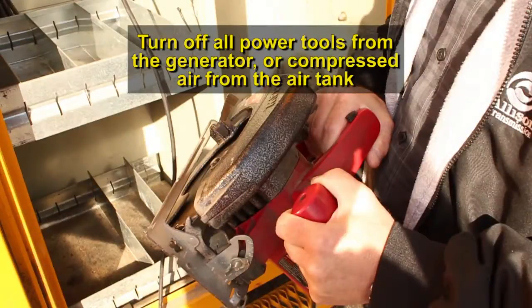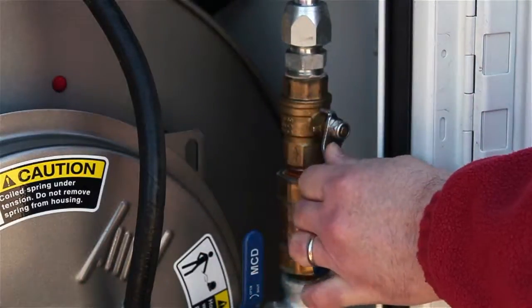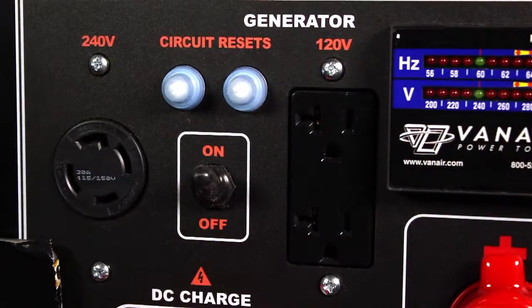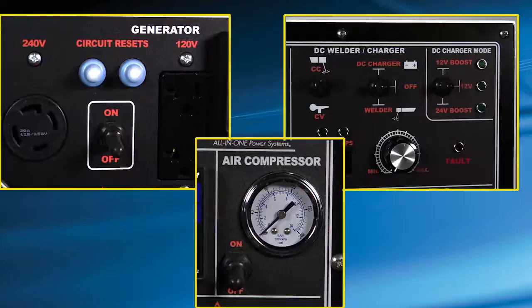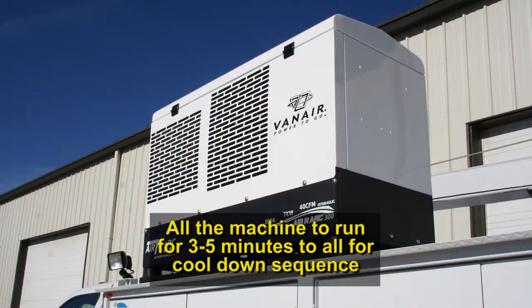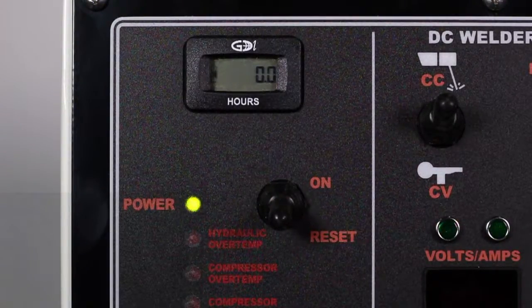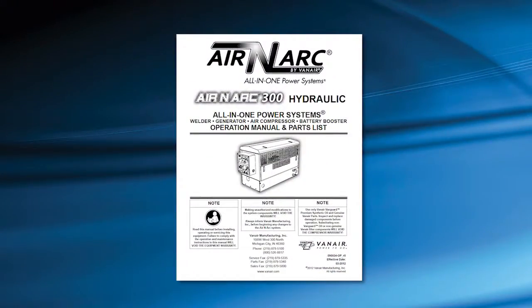When finished using the Air N Arc 300H, shut off any tools or other items that are drawing power from the generator or compressed air from the air tank. Close all service valves. Unplug any power cords plugged into the generator panel. Turn the compressor, generator, and welder switch on the control panel to the off position. Allow the machine to run three to five minutes to allow for a cool-down sequence. Turn the machine's main power switch on the control panel to the off position once the machine has cooled down. Disengage the PTO and turn the truck engine off. For further operating procedures and functions, please refer to your operational manual.